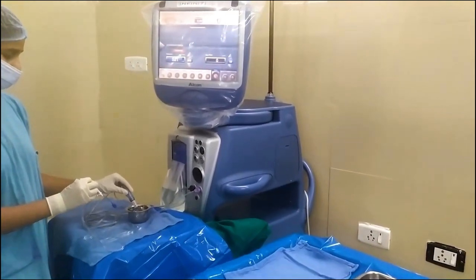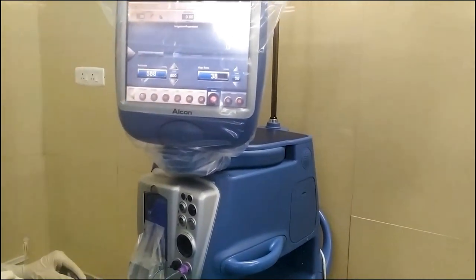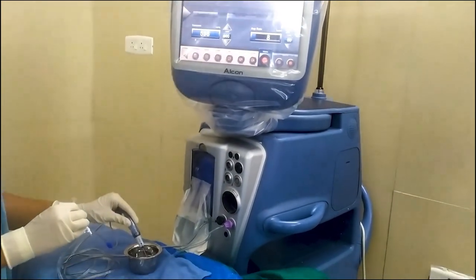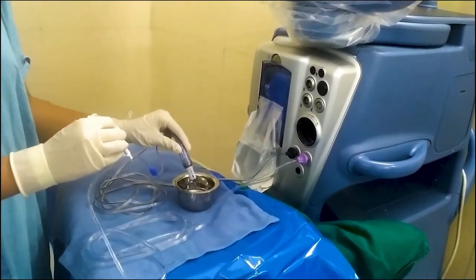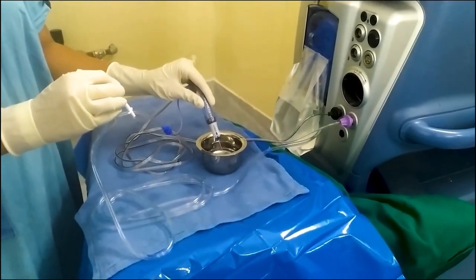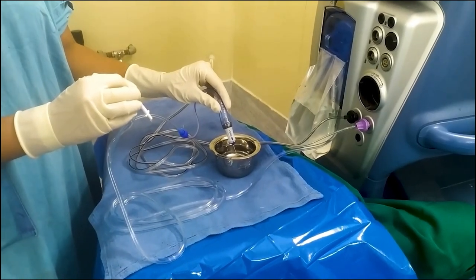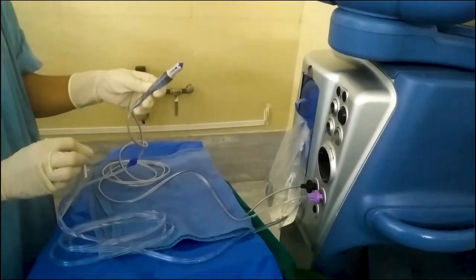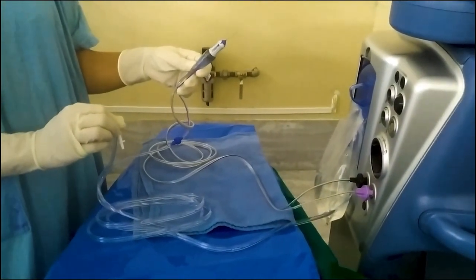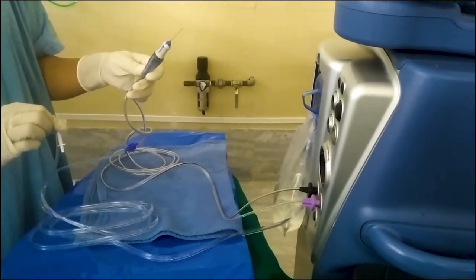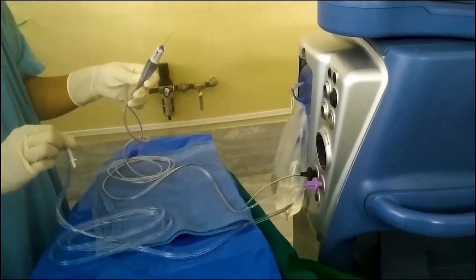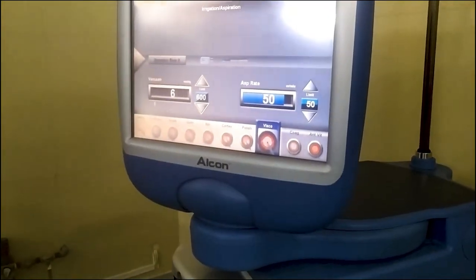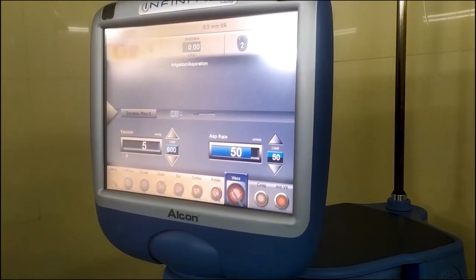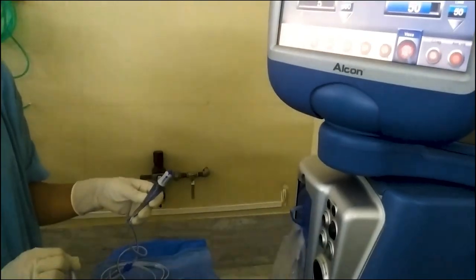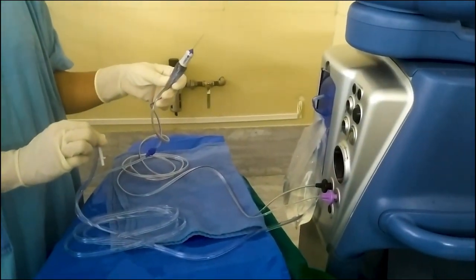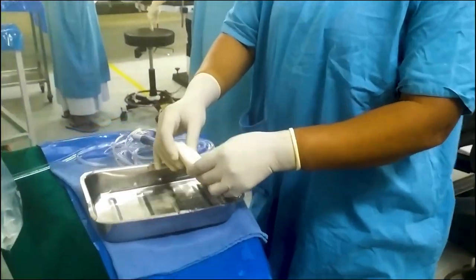We can see the parameters in the phaco machine. It is done in the visco mode. Do it till the bowl is empty. Also, the foot pedal is pressed continuously during that entire process. We can see that the phaco machine is in visco mode during this time. Now the probe is cleaned.